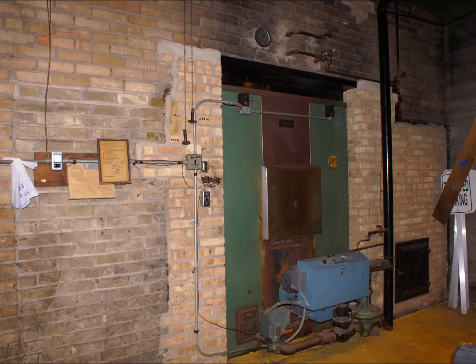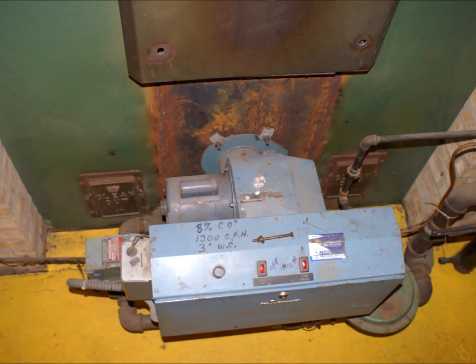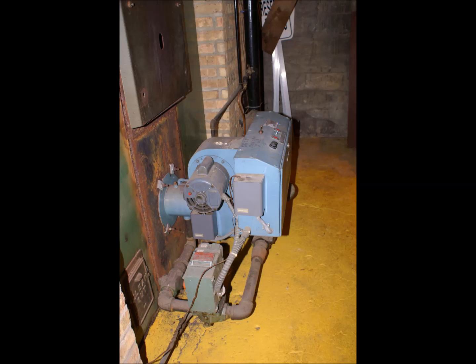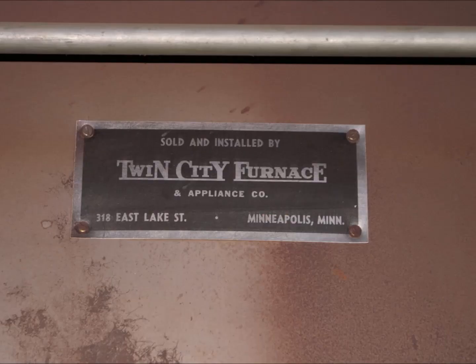You can see where they chopped out a large section of the brickwork and replaced it with a lighter color brick when they did the retrofit to natural gas. The retrofit consists of the large green insert that you see and connected into the original combustion chamber and heat exchanger. Essentially, it was just a big flamethrower attached to the ash collection area below the old coal bed. It was a Synchromatic high-capacity branded unit that was installed by Twin City Furnace.